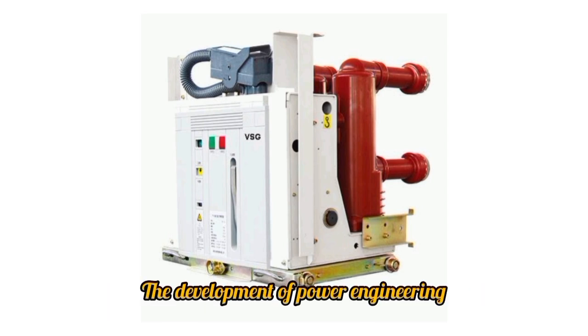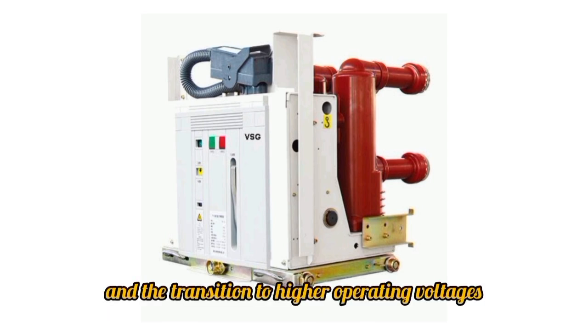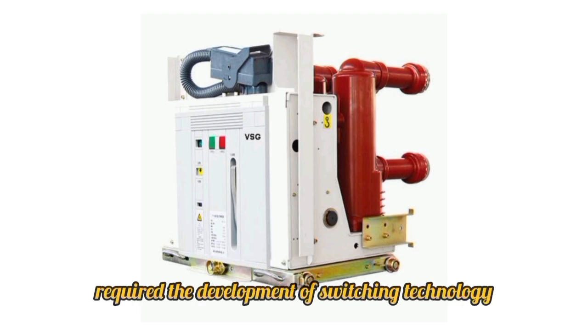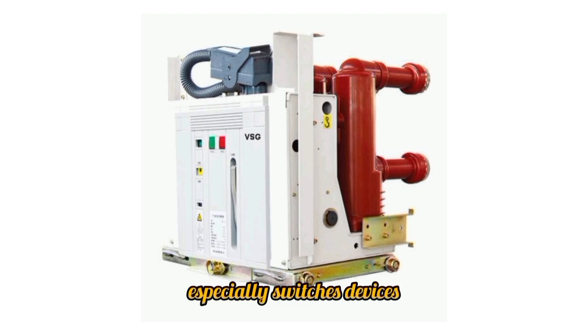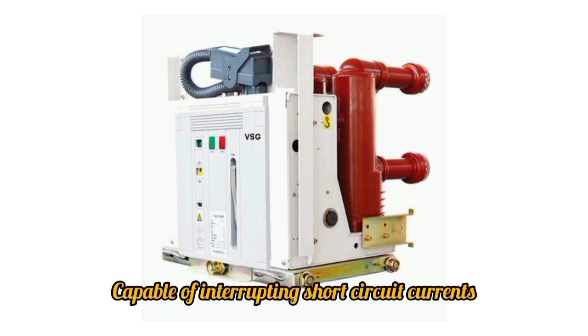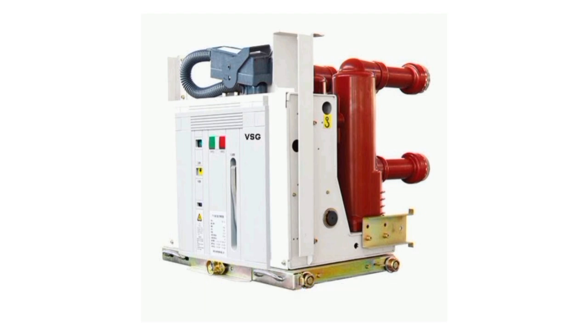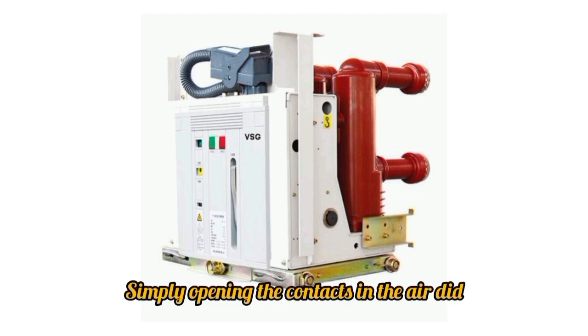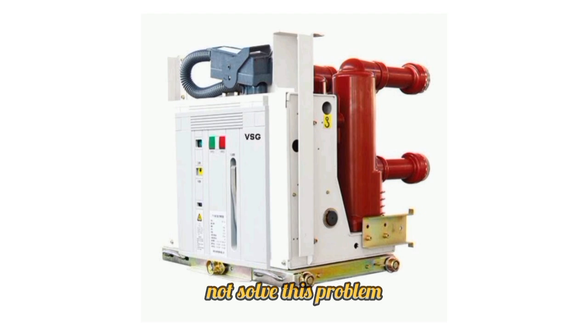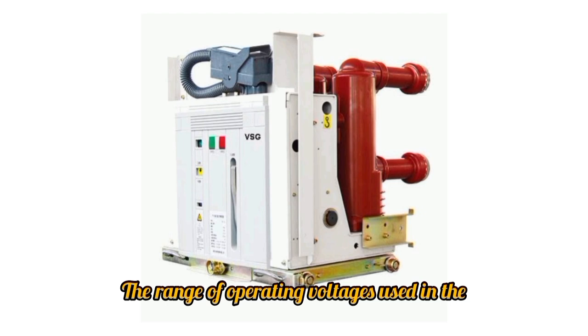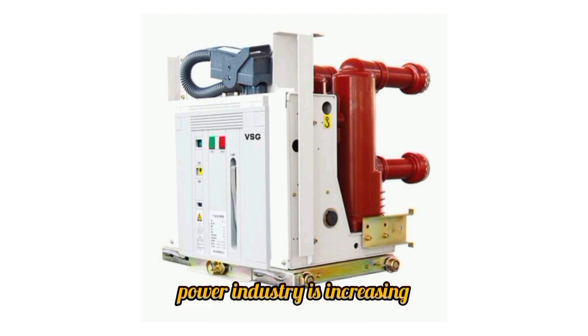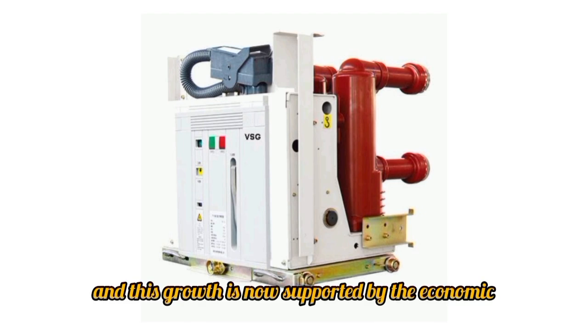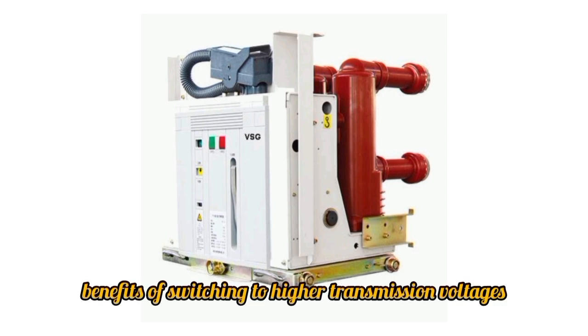The development of power engineering and the transition to higher operating voltages required the development of switching technology, especially switching devices capable of interrupting short-circuit currents. Simply opening the contacts in the air did not solve this problem. New technologies were needed. The range of operating voltages used in the power industry is increasing, and this growth is now supported by the economic benefits of switching to higher transmission voltages.